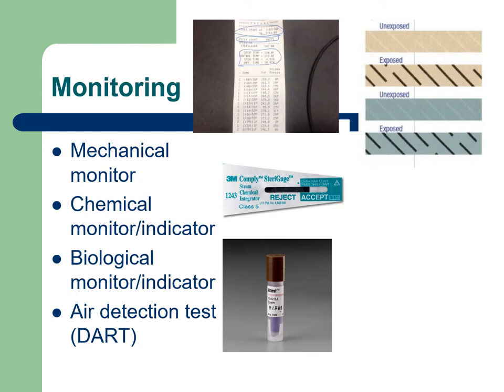This one and what we call the test, which is one we just take out of the drawer, hasn't been cooked, but they're going to become a pair. We're going to push the cap down on the test as well, or the control, and both of these are going to be placed in a special little incubator, and we're going to let them cook for a while. If it changes color, that means the spores are alive. So we expect the control, or the test, to change color. We expect the one that's been cooked is not going to change color. We're hoping all of those spores are dead on arrival. So that's a biological indicator.